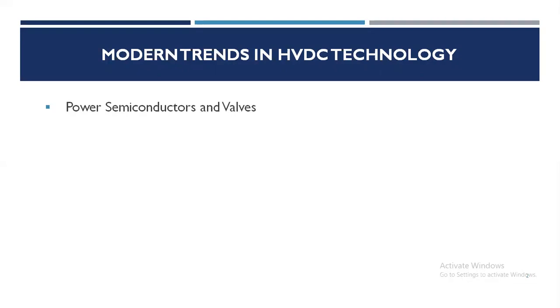The cost of the valve is also reduced by the application of zinc oxide gapless arresters and protective firing methods. Valve design with a suspended structure ensures safety in seismically active locations. The power rating of thyristors is increased by better cooling methods. Deionized water cooling has now become standard and results in reduced losses in cooling.